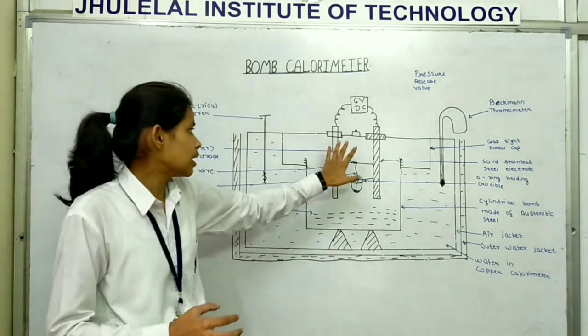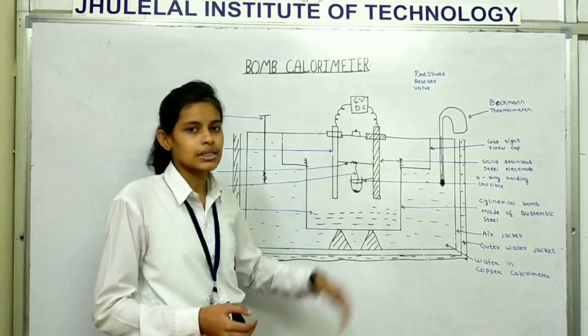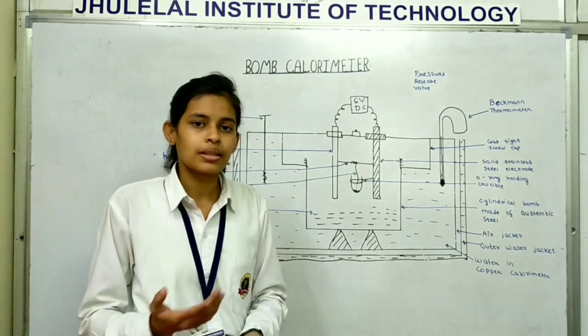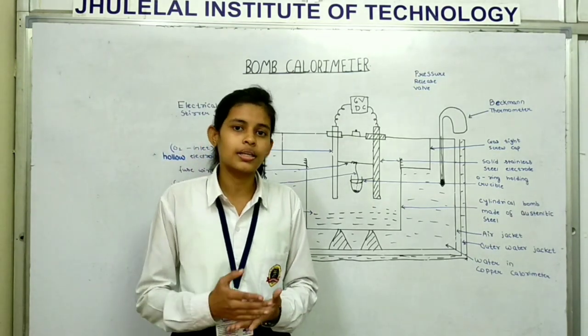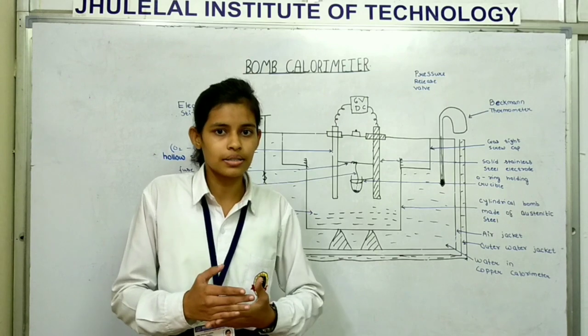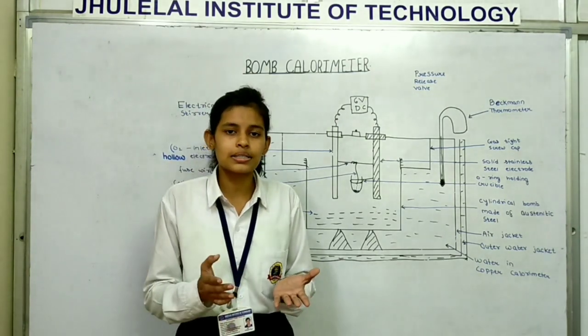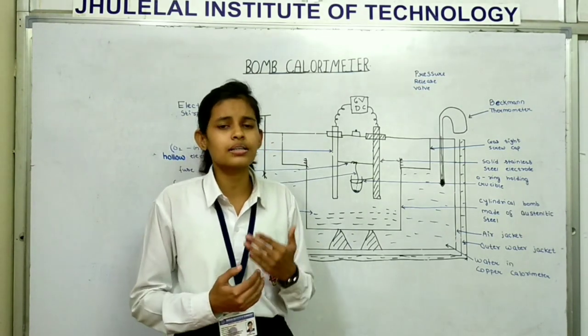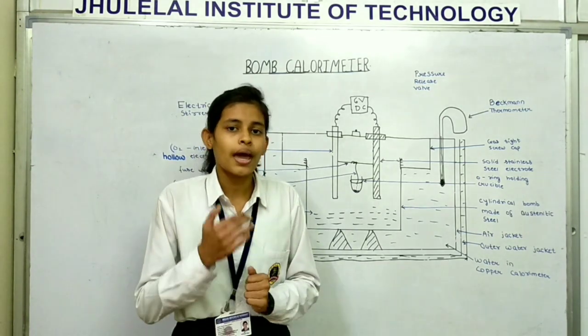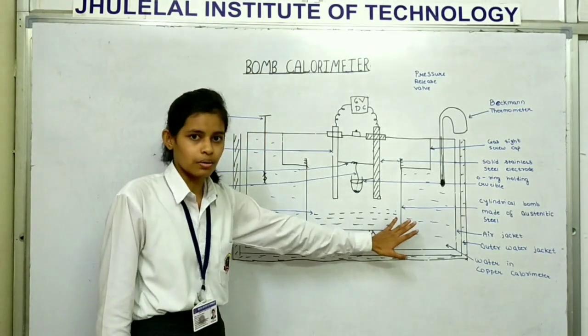The both electrodes are connected to the 6 volt battery and charge is ignited. Then temperature is continuously recorded till the temperature start decreasing at uniform rate. The maximum temperature is the final temperature. The electrical stirrer is stopped and bomb is removed from the copper calorimeter.